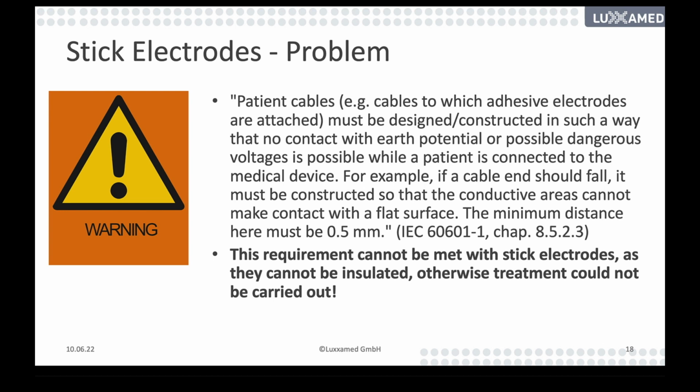So the manufacturer has to ensure that the medical device and of course the spare parts, where maybe the manufacturer isn't the original manufacturer, but in his declaration of the microcurrent device, he has to fulfill the requirements of electric safety. And you have to insulate the metal part in case the electrode falls down.